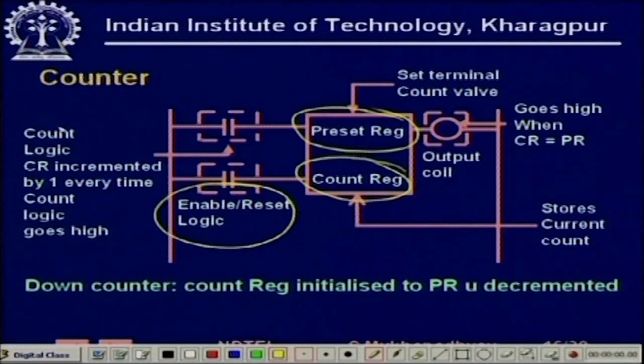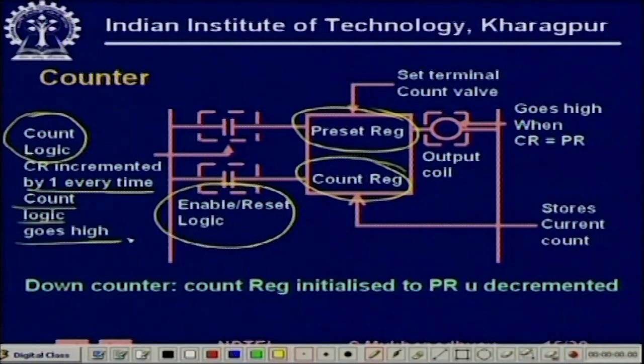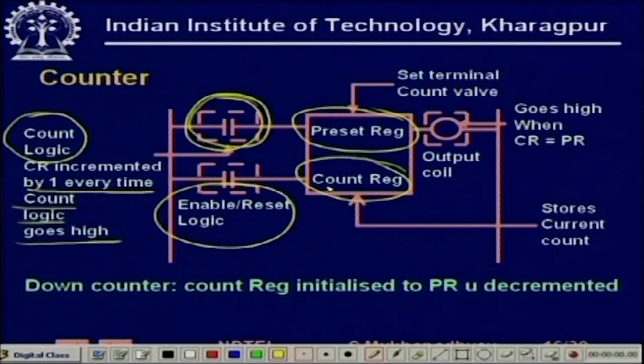Again you have enable and reset logic, same as the timer. In this case we have what is known as count logic rather than timer run logic. The count register is incremented by one every time the count logic goes high. When the count register value exceeds the preset register value, the terminal count is reached and the output coil goes high.